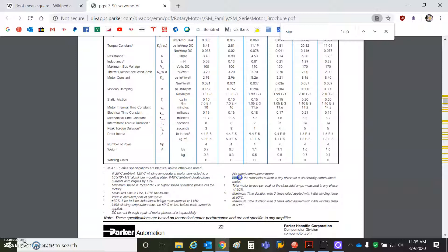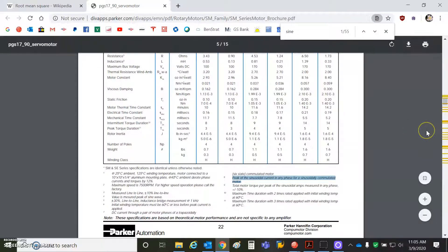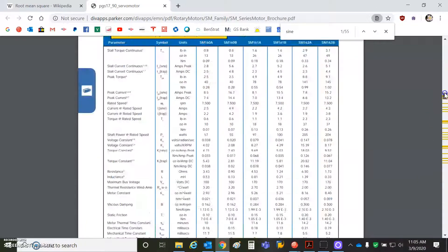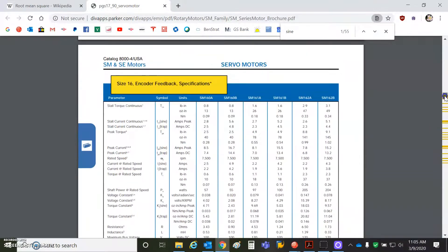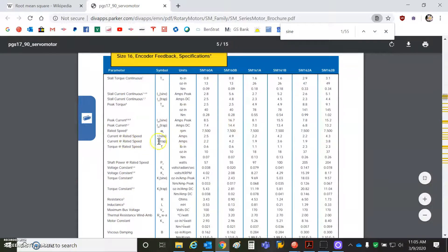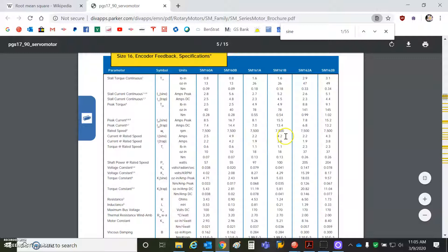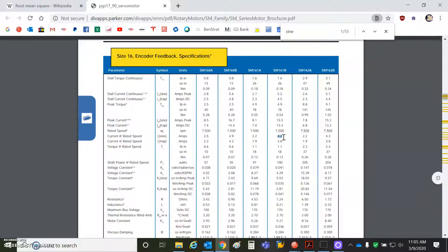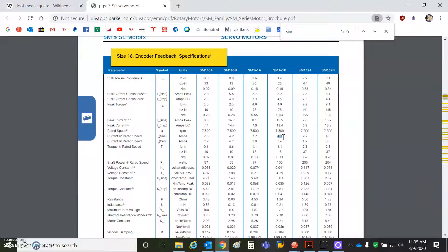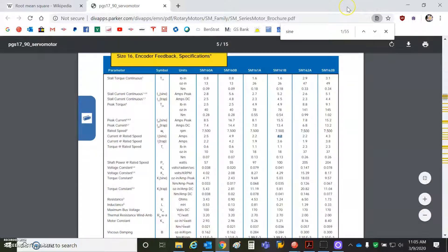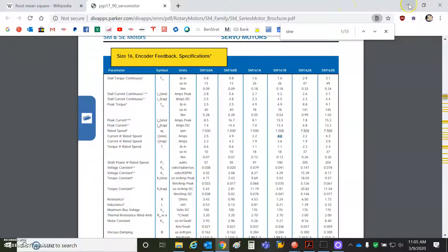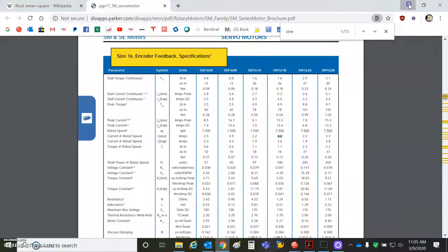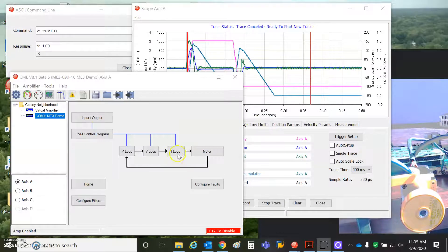So this is the peak of the sinusoid current in any phase, sinusoidally commutated. So the 5.2 amps is a little optimistic. I would go with the rated current in amps, so 4.2 amps, peak of the sine. And that's the value you would normally put into the Copley, not the RMS value, but the peak of the sine. So when we say amps, we're talking peak of the sine, not the RMS. And if a motor manufacturer said 5 amps RMS, you multiply that by the square root of 2 or 1.414 and enter that value into the Copley.